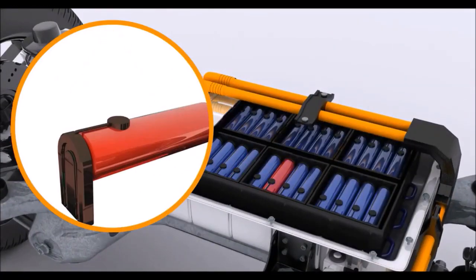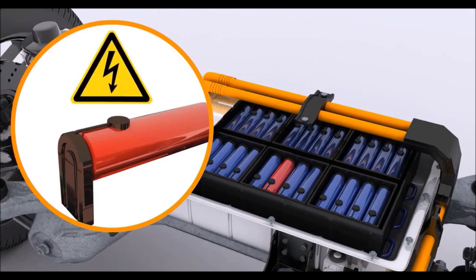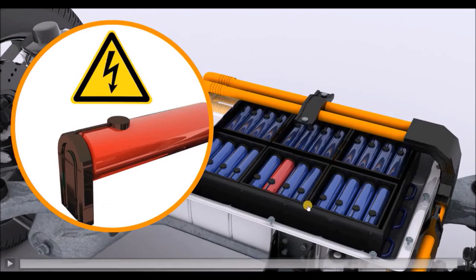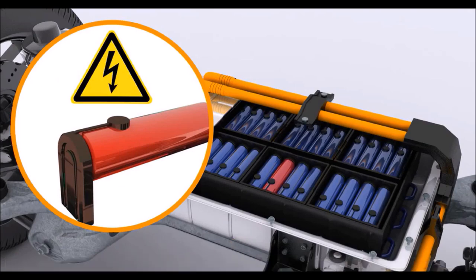There you see you get one temperature warning from one cell, or respectively from one temperature sensor. When there's really a thermal issue, you won't just have an alarm from one sensor. So especially over time, when nothing changes in this warning situation, most probably there won't be a damaged cell, but rather a broken temperature sensor. Of course you still have to do the work, open the high voltage battery and exchange the temperature sensor, but it's not a critical fault.